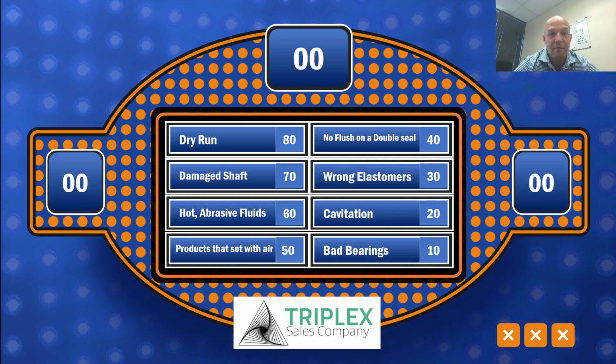If we're seeing drive deflection, shaft deflection, that obviously is going to impact our seal life. Our mechanical seals are riding on a shaft. Ultimately, they, by name, are a shaft seal. And if our shafts are deflecting, then those seals aren't going to ride right. You're going to have uneven wear, and you're going to have premature failure. So that's it. Those are our top 8 reasons, Family Feud style, for why we see reduced seal life in PD pumps, or why we have problems with mechanical or O-ring seals in Waukesha PD pumps or any sanitary pump.